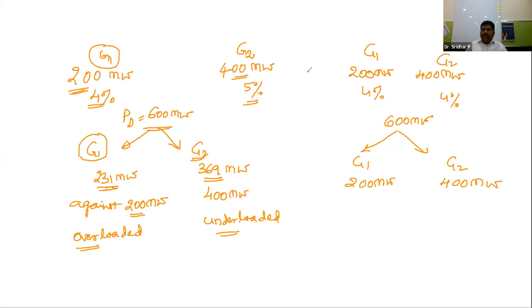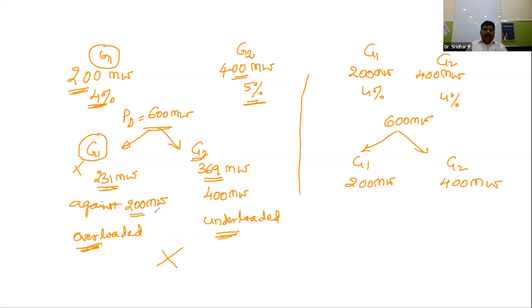When droop characteristics are unequal, one generator gets overloaded and the other gets under-loaded. The overloaded generator suffers because the excess 31 MW generates too much heat. If temperature exceeds the insulation's acceptable limits, there is a serious threat to the insulation and the machine itself.